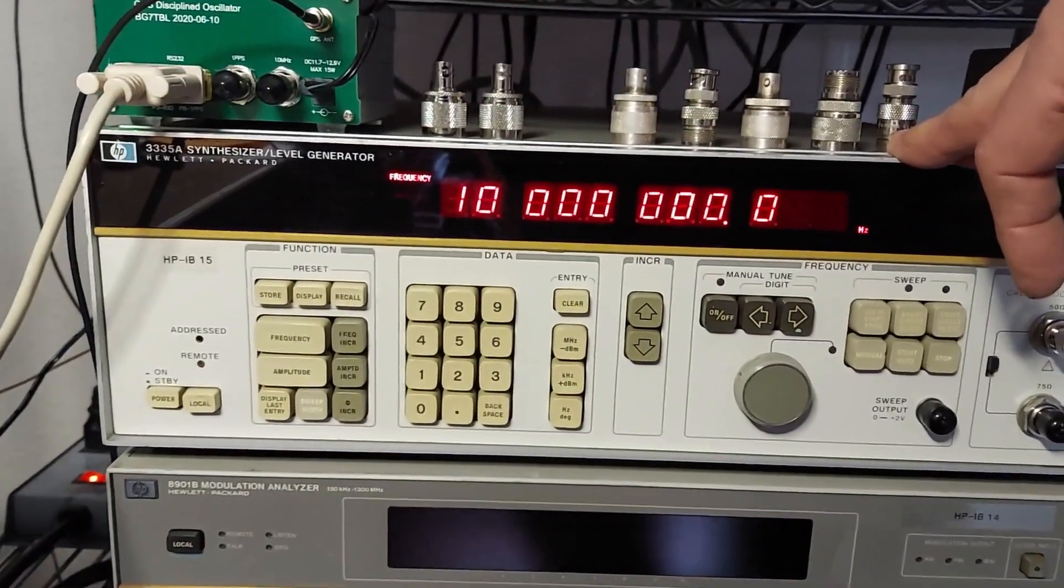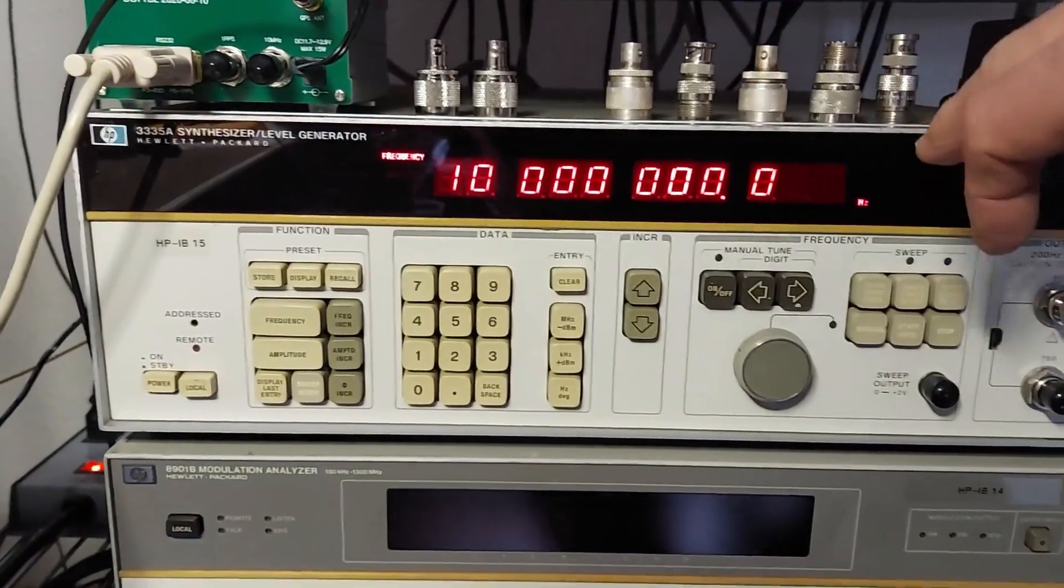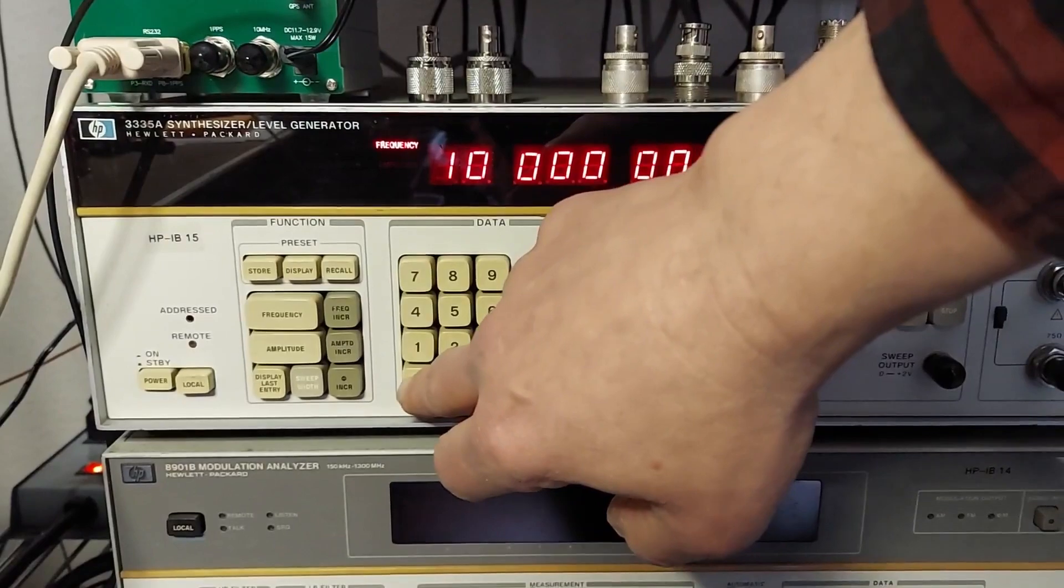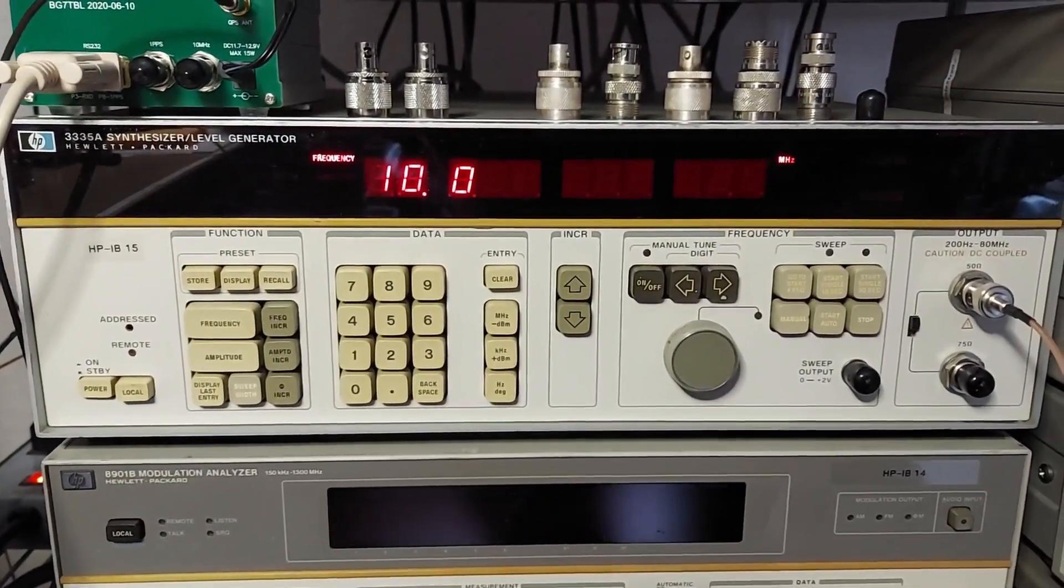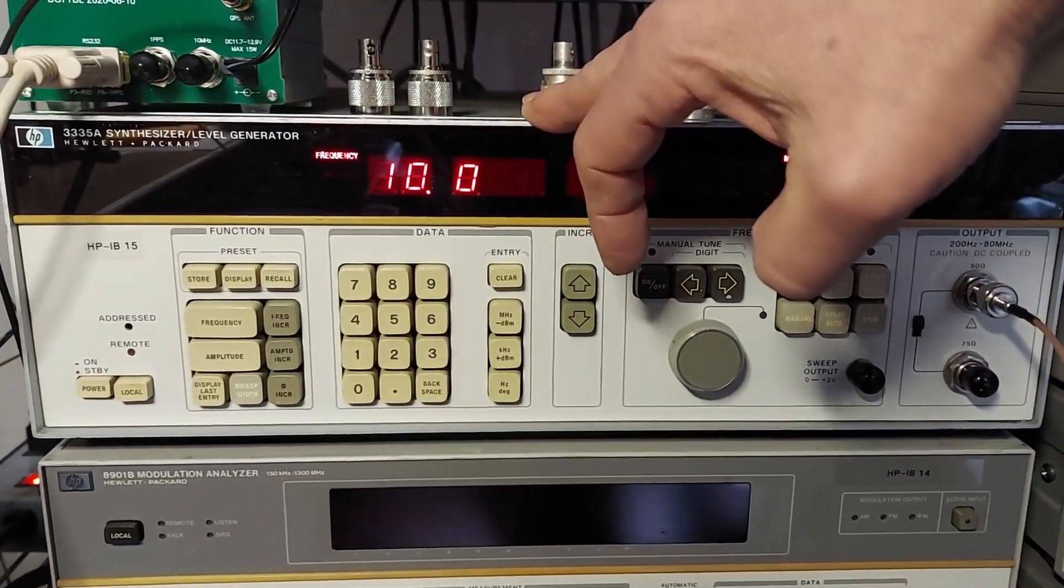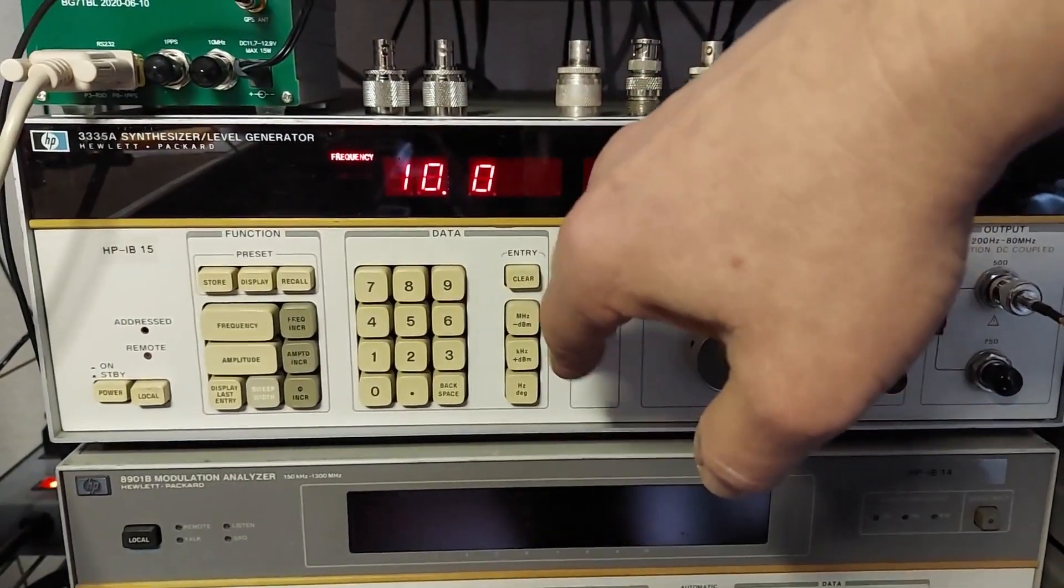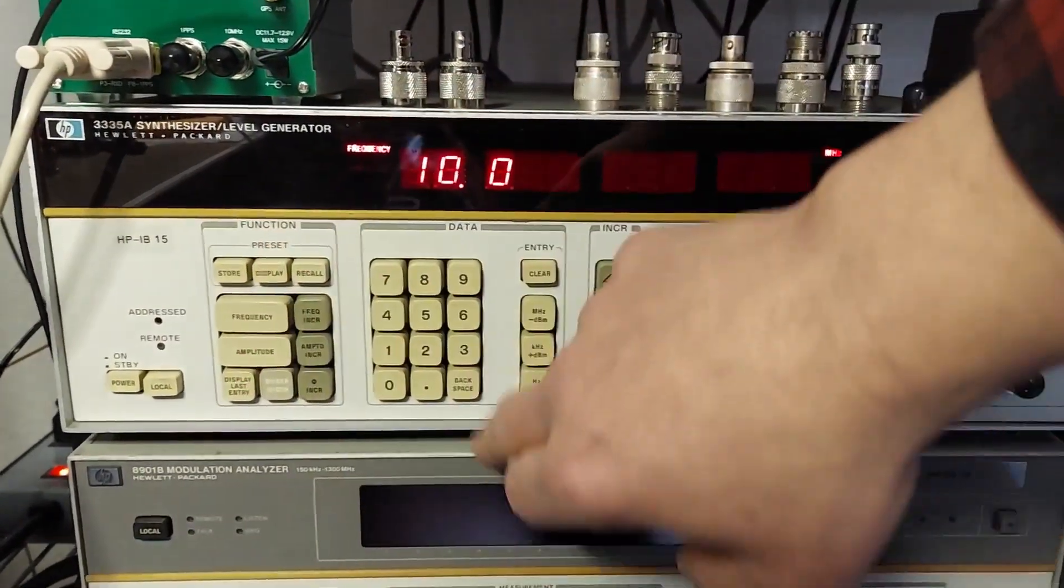When you set presets it will store - you have 10 registers 0 through 9 - and it will store all of the operational parameters. So say I want to recall register 0, I press recall 0 and all the parameters I had set in there are right back where they were. Now if I want to display the parameters of a particular preset but I don't want it to take effect, then I press the display button.